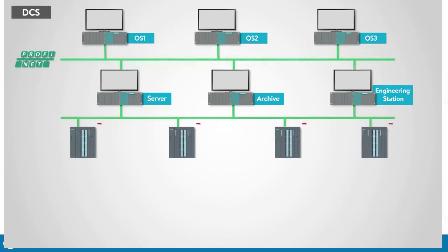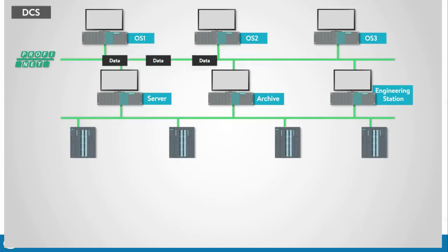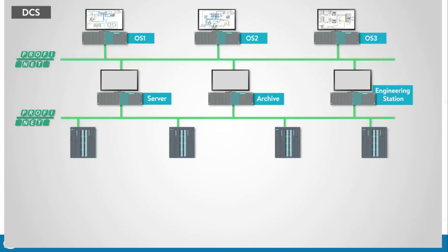At the next level, you have the master controllers that supervise the individual processors as well as I/O modules. These controllers are also responsible for providing the data to the servers, which in turn supply the data for the graphical interface. Industrial Ethernet is typically used for communication with the previous level; fiber optic may be used where Ethernet cabling runs would be too long. At this level, the processor executes the logic and does what it needs to do in order to control the process.